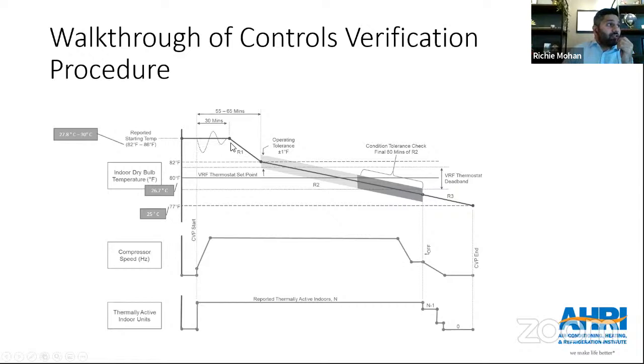What you see over here is a stabilization period, such that the unit is getting acclimatized to the ambient temperature. In addition, the test chamber itself is making sure that the overall temperature in that chamber is uniform. While the stabilization is taking place, on the compressor side you see the compressor turning on and ramping up to the desired state, and it will then stay the same as long as we don't change the outdoor ambient temperature. At the same time, you also see the indoor units all turn on once the system has had enough time to react to the overall temperature.